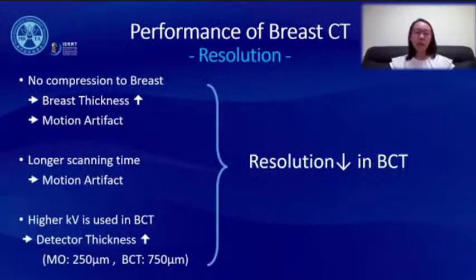Okay, let's have a look at the performance of resolution in breast CT compared to mammogram. Since there is no compression of the breast, the breast thickness in the CT is higher, and this increases the possibility of motion artifact, and we have a longer scan time compared to mammogram. It also probably makes the motion artifact possibility higher, and we use a higher kV in breast CT to pass through a thicker breast. So the detector thickness is increased at this point. So overall speaking, the resolution in breast CT is lower than in the mammogram.